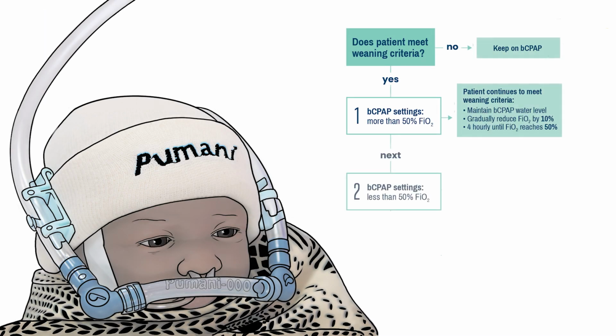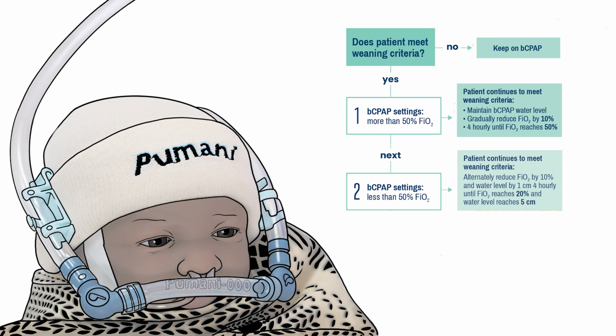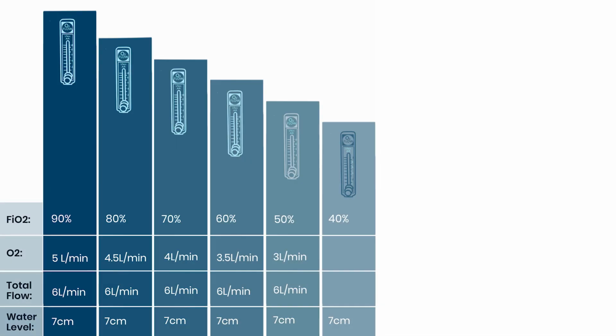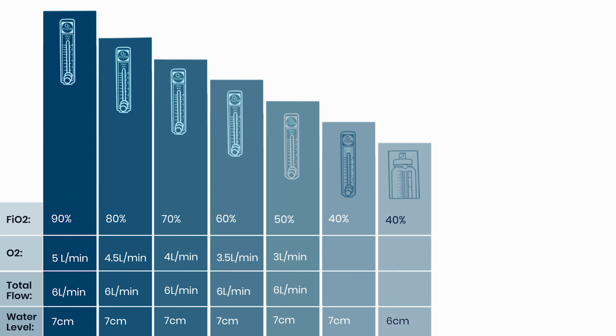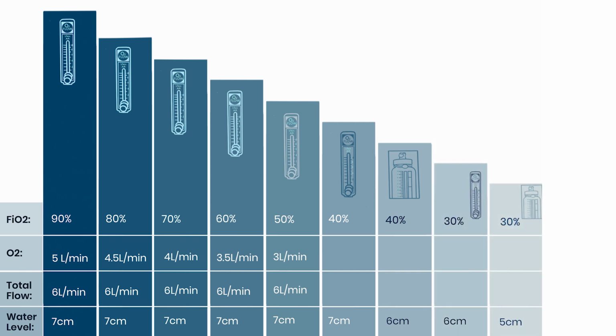Once you reach 50% FiO2, the next stage is to reduce the oxygen flow rate and the level of water in the bottle alternately every 4 hours. You do this until you reach 20% FiO2 and the water is at 5 centimeters. So let's go back to our example. This will be the next steps down. First, the FiO2 to 40%, then the water to 6 centimeters, then the FiO2 to 30%, and next the water to 5 centimeters, and finally the FiO2 to 20%.